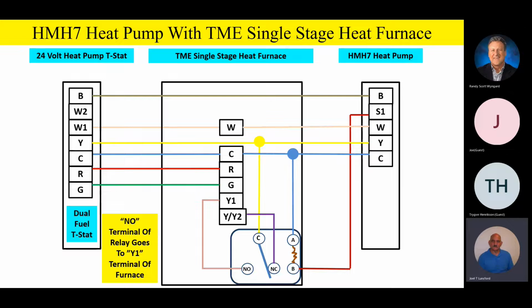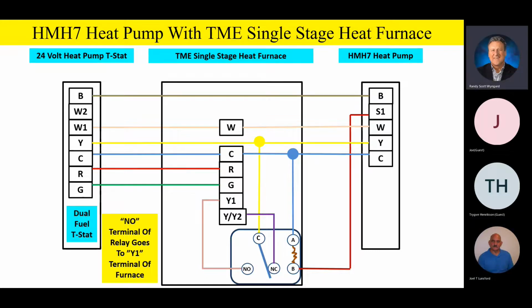Does that make sense? Basically, if that ECM motor sees more than one call as far as speed input, it'll always take the highest input. So based on the furnace model, and the tonnage of the outdoor unit and so on, when it sees a W call, if that W is higher than the current airflow call, it'll drive it to that higher call. Good question. Did that answer your question okay? Yeah. Thanks, Joel. Okay. There you go.